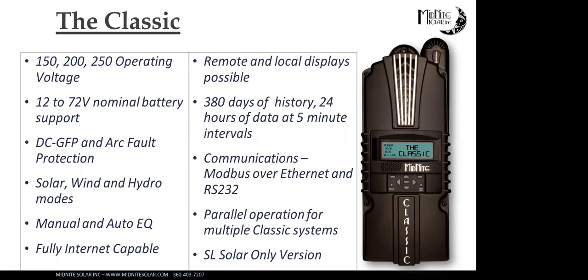The Classic stores 380 days of daily history, and then it stores 24 hours of minutely history. So at the end of every day, it takes the kilowatt hours for the day and the high battery voltage and things like that, and stores that for 380 days. But every 5 minutes, it will take a snapshot of everything that it's doing, and it just overwrites that. So it stores the last 24 hours.